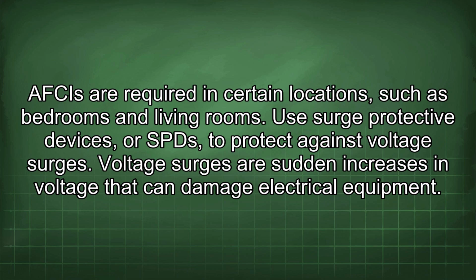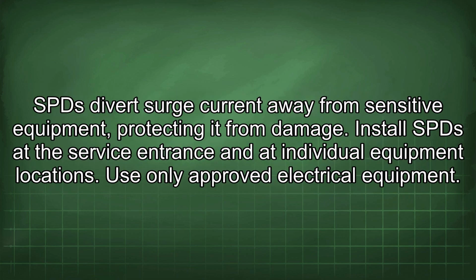Use surge protective devices, or SPDs, to protect against voltage surges. Voltage surges are sudden increases in voltage that can damage electrical equipment. An SPD diverts surge current away from sensitive equipment, protecting it from damage. Install SPDs at the service entrance and at individual equipment locations.